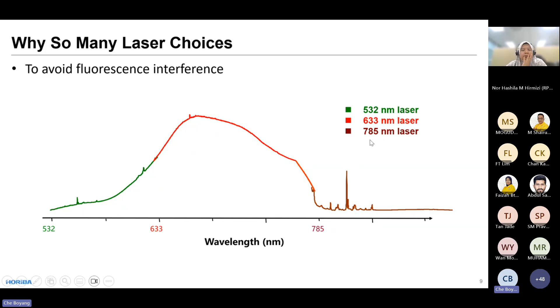That's why we provide different wavelength lasers, so that you are able to get rid of the fluorescence interference and observe more Raman signals from your sample. Sometimes when you cannot get your signal using the 532 laser, you can try shifting to another laser, 785 or even higher, to see if you can get a signal.